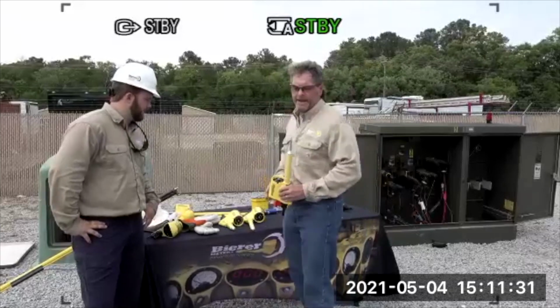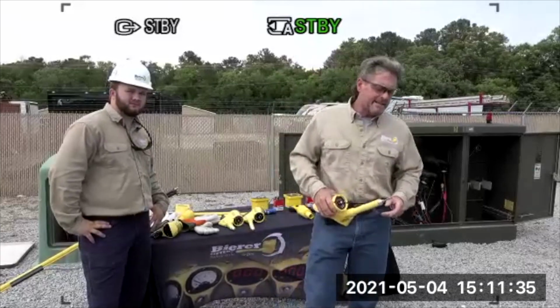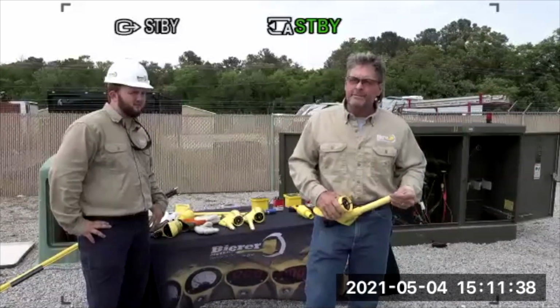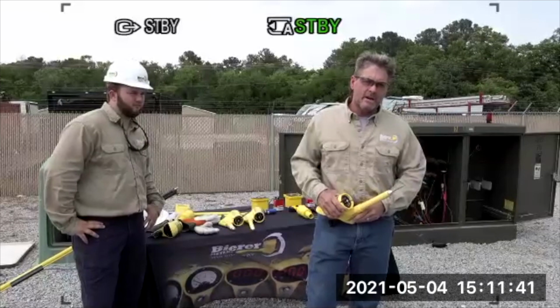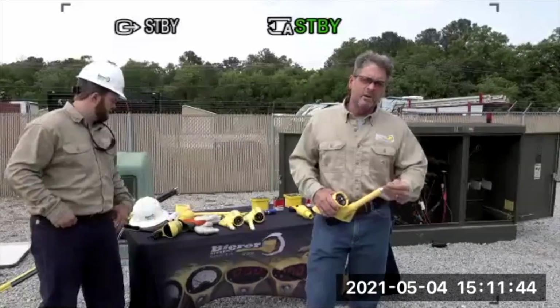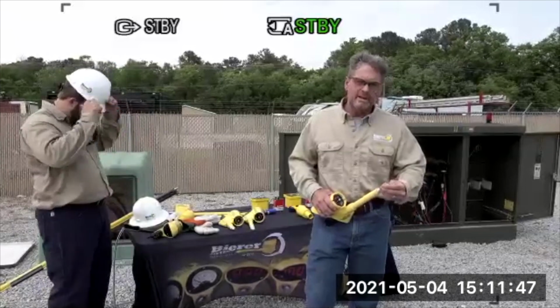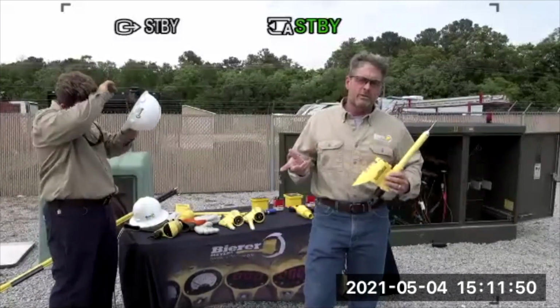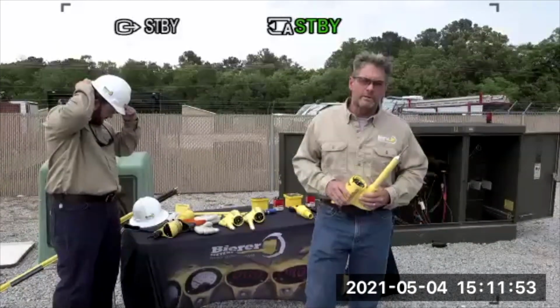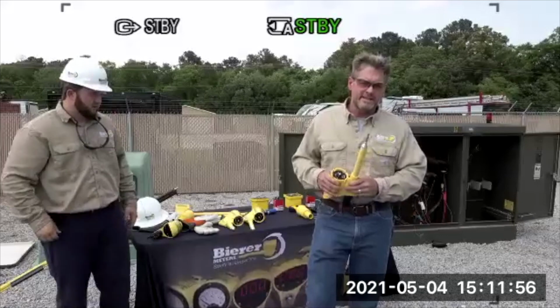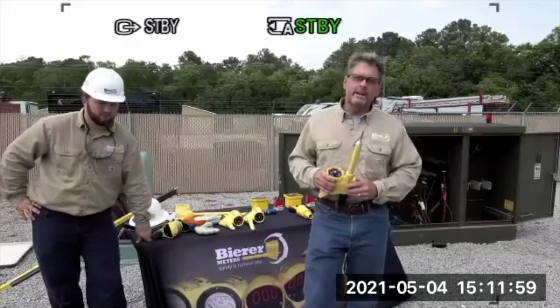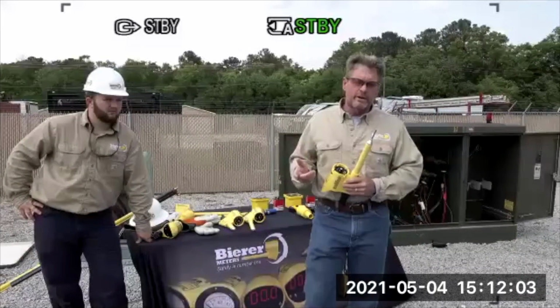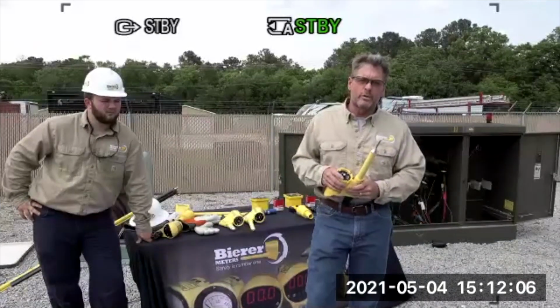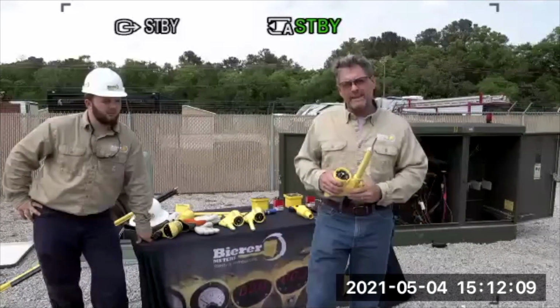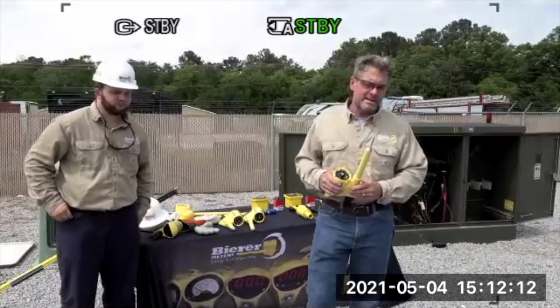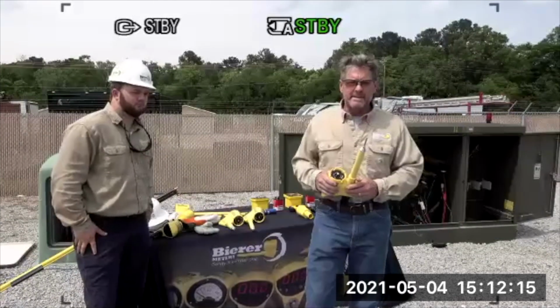So what we're going to do is look at 1910.269 in OSHA - if you go down to lowercase n, it talks about temporary personal grounds. In lowercase n, before the grounds are applied, the line worker is supposed to check for a lack of nominal voltage on the conductor prior to placing his temporary personal grounds. We train that not only are we going to check for a lack of nominal voltage, but we're also going to look for a lack of induction and a lack of backfeed with our tool prior to placing our TPGs. Does that make sense to everybody?